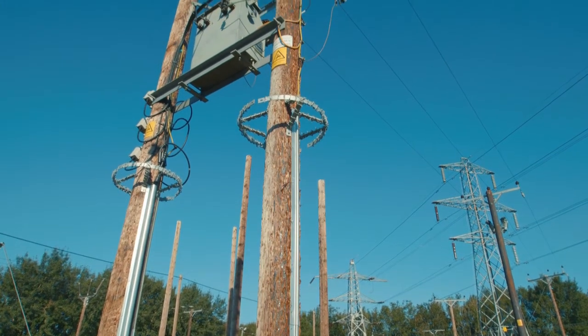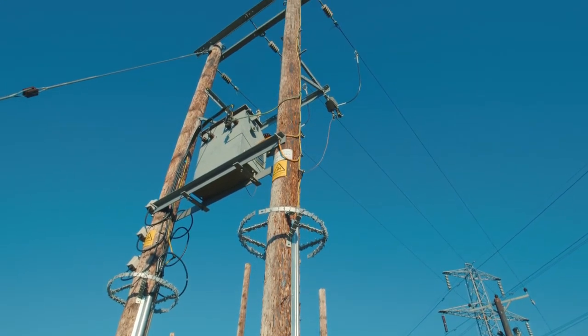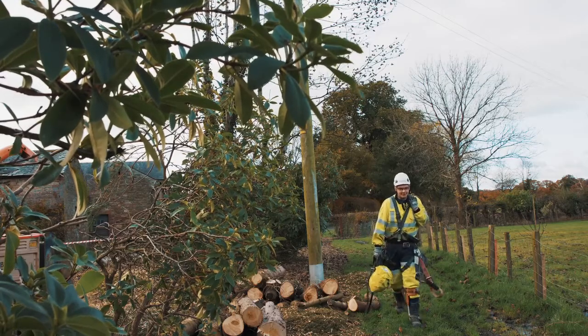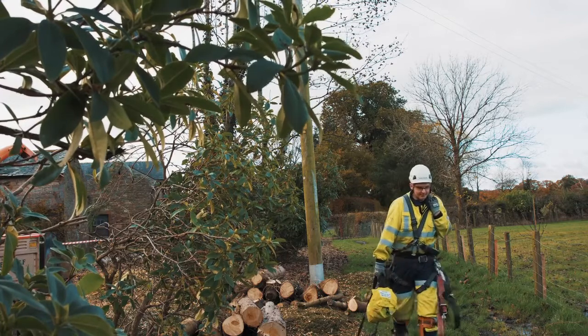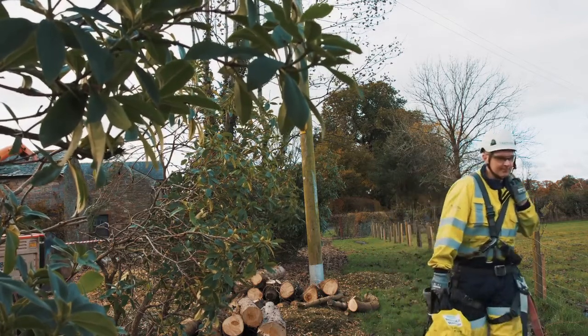We identified 12 circuits actually. These circuits were selected on fault history, because with it being a fault detection system, you want to actually have faults to prove the concept or prove the technology. And on those 12 circuits, we're looking to deploy a total of 150 units. To date, we've installed 110 units so far. We've got some down in the Peak area, down in Lancashire, and in Cumbria. So right across, trying to get that diverse sort of topology across all circuits.